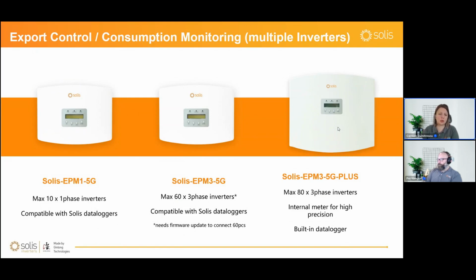But when you have multiple inverters, you're going to need an EPM, Export Power Manager device. We have 3 types of these devices: Solis EPM1-5G. This is a single phase EPM, so it will be compatible with single phase inverters. It can control up to 10 devices connected through RS485 to it. Then we have Solis EPM3-5G. This is an EPM which is compatible with 3-phase inverters and can connect up to 60 devices.